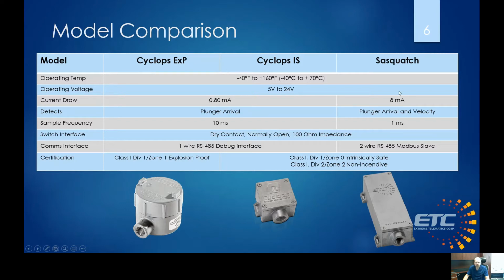Now you'll notice here the Sasquatch uses about 10 times the amount of current, and that's because we sample at 10 times the frequency. Because we need to get higher resolution data when a plunger is moving by the sensor, we're actually looking at how fast the plunger moves from one end of this sensor to the other. We have to sample at a much higher frequency. So we're sampling at 1 millisecond on 2 sensors. It does have an operational interface. It's got a 2-wire RS-485 interface that acts primarily as a Modbus slave, but once again, it can also mimic this debug interface for use with Vision.